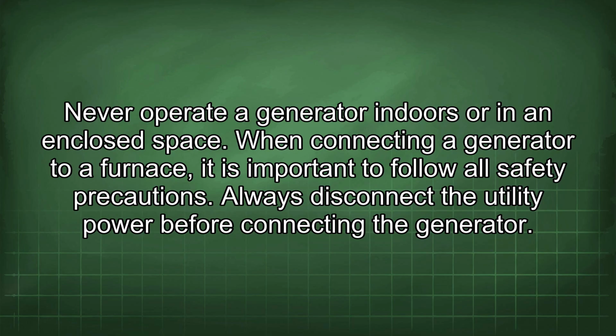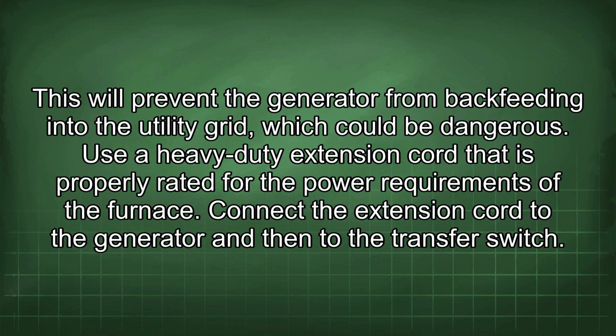When connecting a generator to a furnace, it is important to follow all safety precautions. Always disconnect the utility power before connecting the generator. This will prevent the generator from backfeeding into the utility grid, which could be dangerous. Use a heavy-duty extension cord that is properly rated for the power requirements of the furnace. Connect the extension cord to the generator and then to the transfer switch.